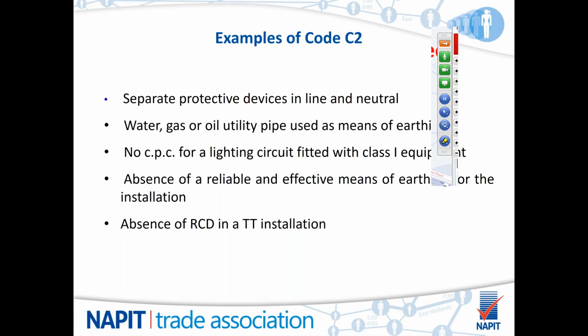We've already mentioned that water, gas and oil pipes need to be bonded. Utility pipework can be used as the earth and was used as the earth in older installations. And if this is the case, of course, it's C2. We've now got no proper earthing to the building. If there's no CPC for class 1 metal light fittings, the light fitting as it stands will not hurt anybody. If something happens to that light fitting and it becomes live and somebody touches it, then it will.